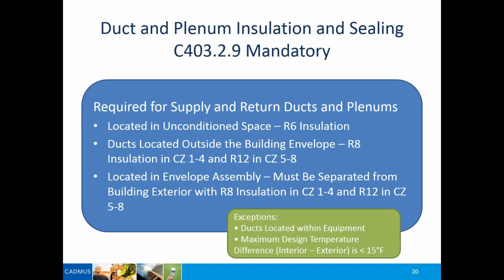Typically, ducts that are inside the building in conditioned space do not have to be insulated. There is a requirement in the code right now with a threshold that essentially says if there's a greater than 15-degree temperature difference between the ambient air that the duct passes through and the airflow in that duct, then you should insulate the duct system. But if you look at the International Code Council interpretation in their commentary, they're essentially saying, as ASHRAE does, that ducts in conditioned space do not have to be insulated. So it's slightly different from the code language, but that's the way it's been interpreted.